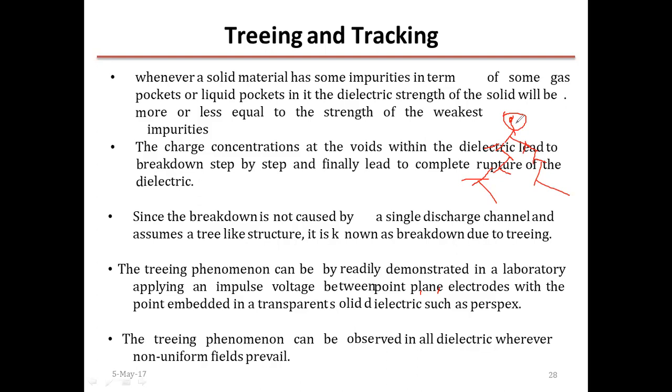Whenever a solid dielectric has some impurities in terms of gas pockets or liquid pockets, the dielectric strength of the solid will be more or less equal to the strength of the weakest impurity. Since the breakdown is not caused by a single discharge channel and assumes a tree-like structure, it is known as the tree effect.